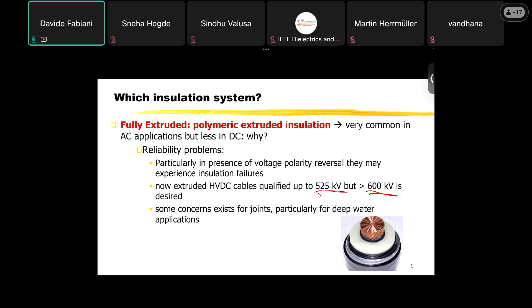And then the reliability problems that this kind of insulation has are related or associated with space charge accumulation. At the end of the 90s, someone wanted to use the XLPE material that was used for AC applications for DC application. And the problem was that the AC cable fed under DC, even at low electric field, let's say not very high, say 10 kilovolt per millimeter, after a few tens of hours of service, as you can see here, 60 hours, the cable failed.